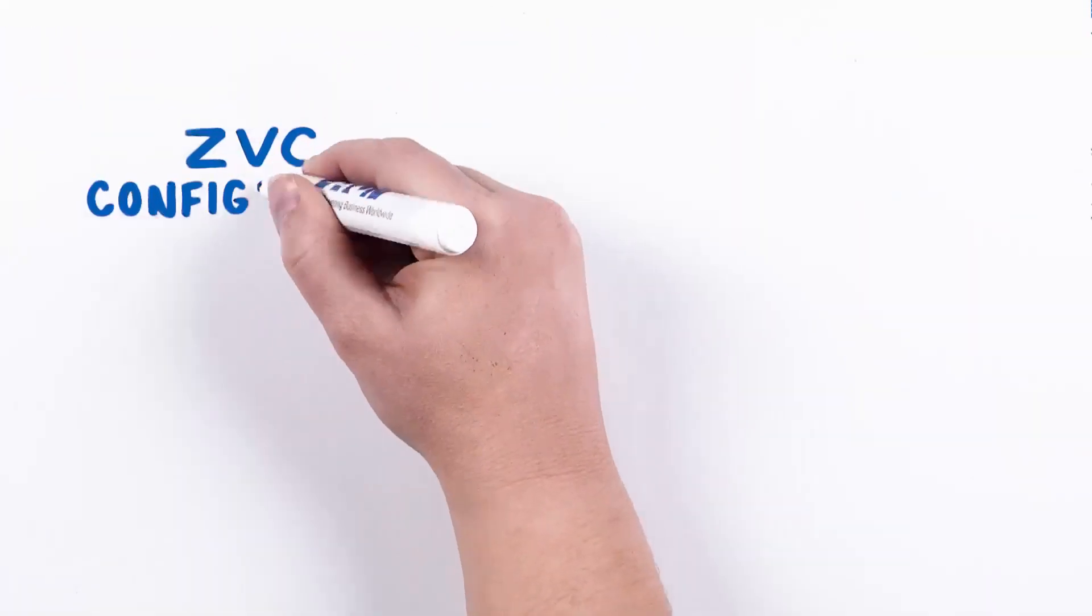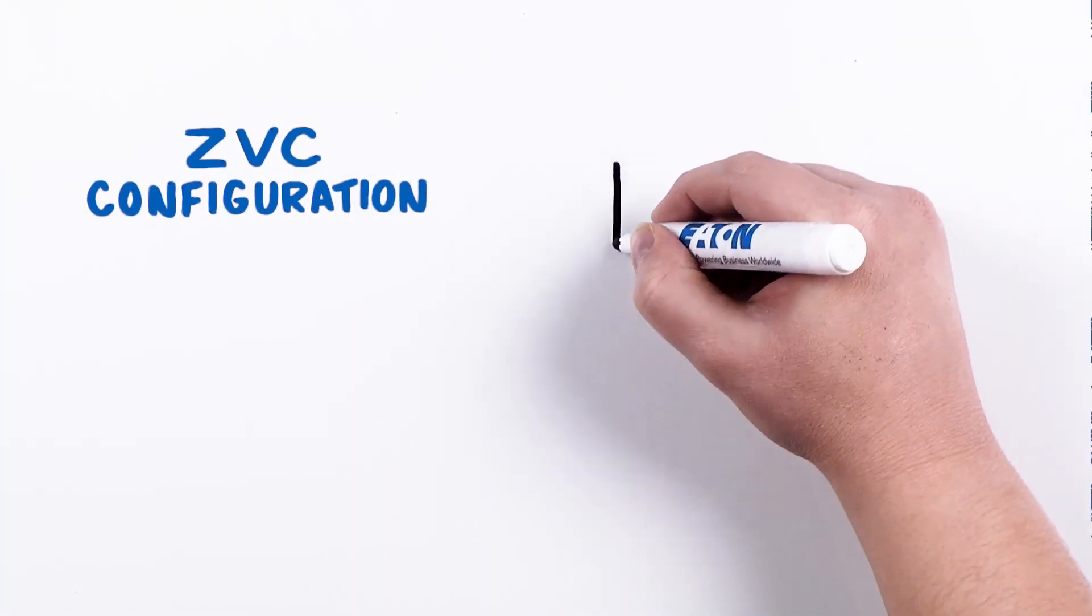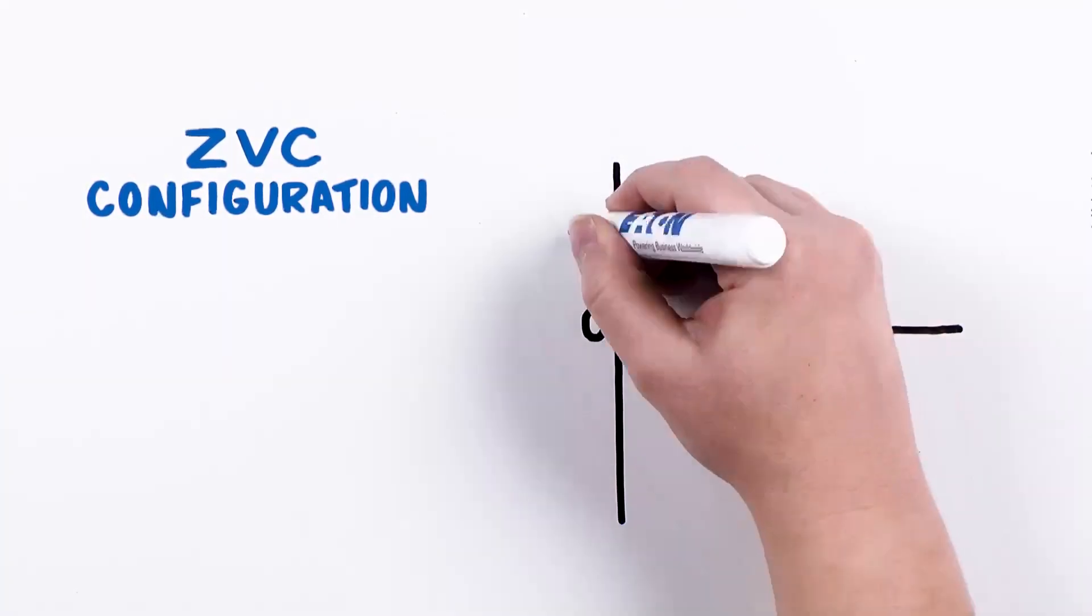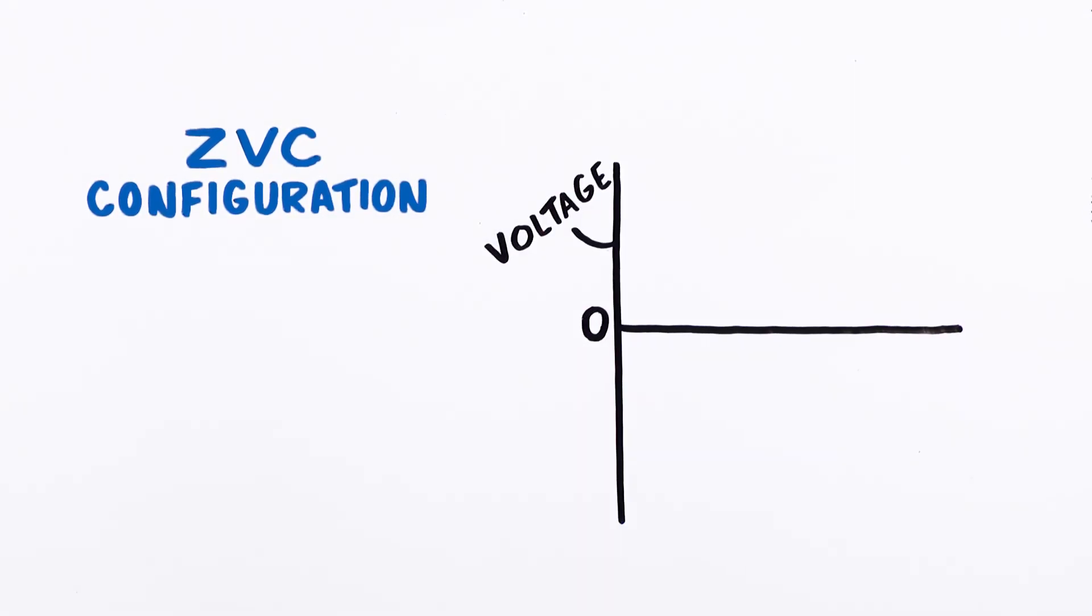The ZVC configuration monitors system voltage, closing each phase as it crosses zero voltage to minimize resultant transients.